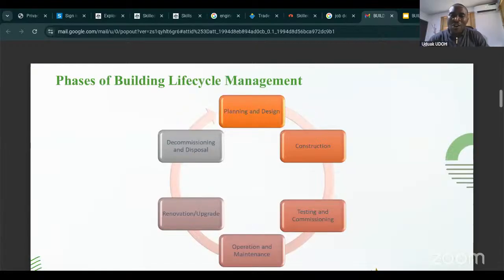So testing is always critical. Testing is about testing for functionality. It starts technically and also administratively. First, technically, it starts with: from which source was the AC power looped from? Was there a circuit breaker there? To test the breaker, is there a continuity test? The voltage to check, is it complete phase, maybe a single phase or a three phase, then the multimeter is always used to check.